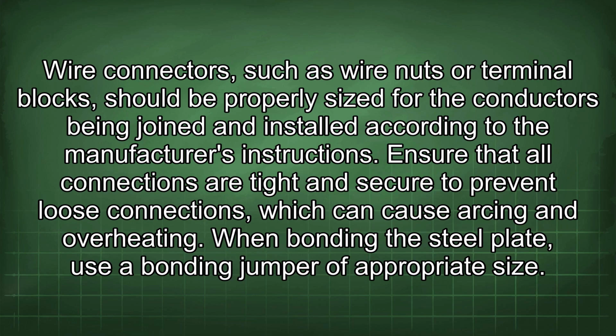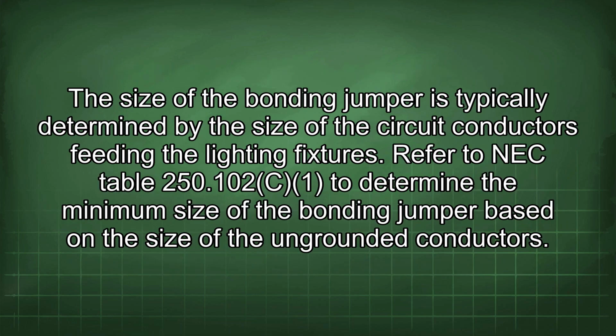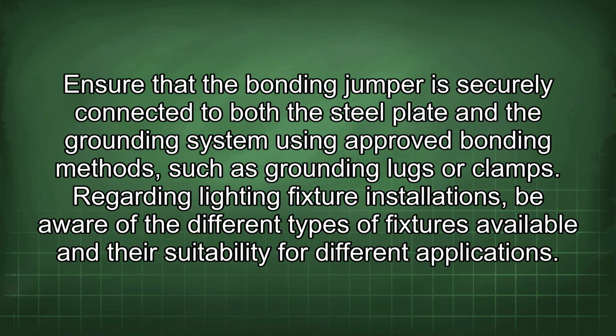When bonding the steel plate, use a bonding jumper of appropriate size. The size of the bonding jumper is typically determined by the size of the circuit conductors feeding the lighting fixtures. Refer to NEC Table 250.102(C)(1) to determine the minimum size of the bonding jumper based on the size of the ungrounded conductors. Ensure that the bonding jumper is securely connected to both the steel plate and the grounding system using approved bonding methods, such as grounding lugs or clamps.